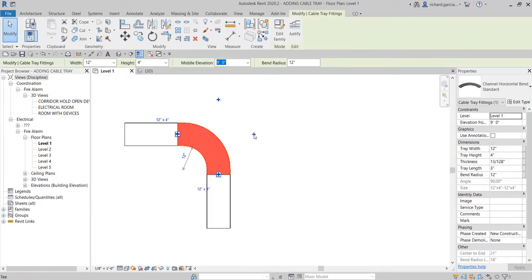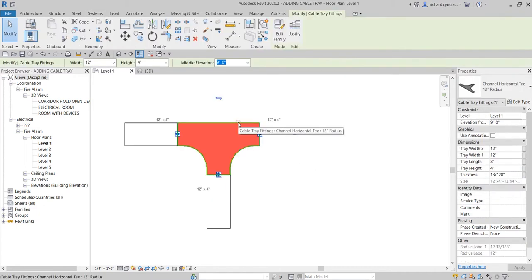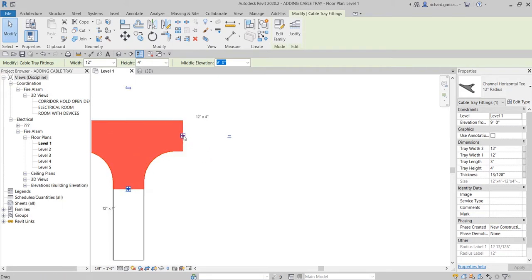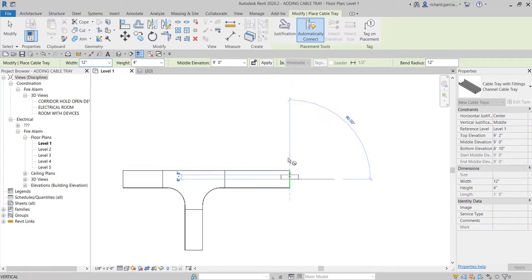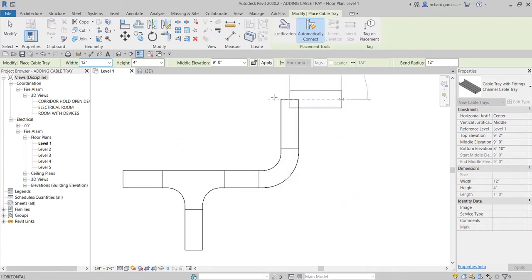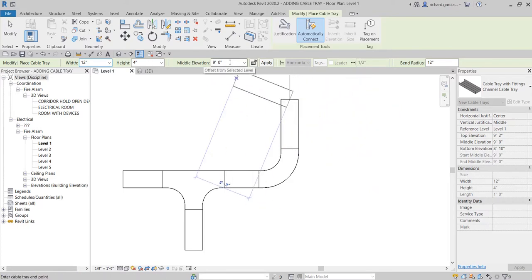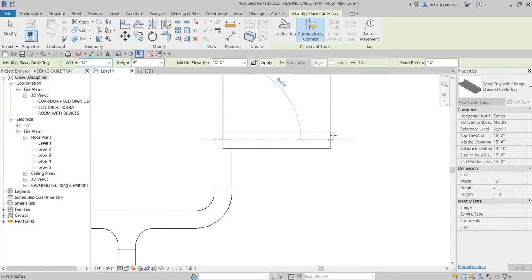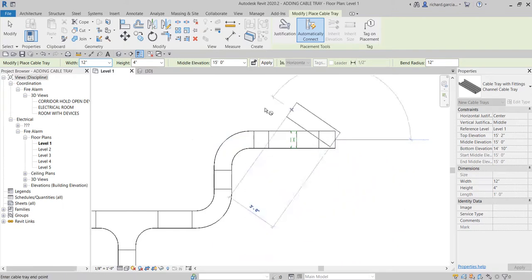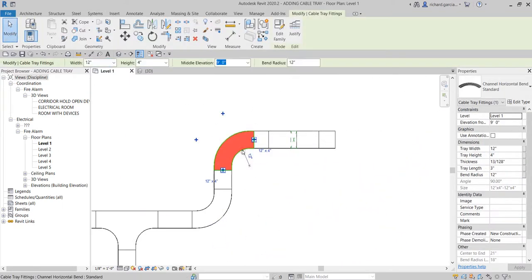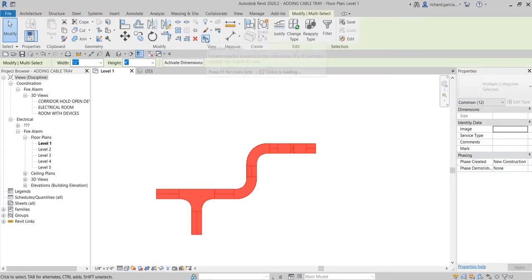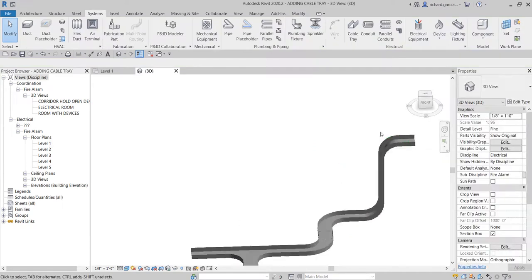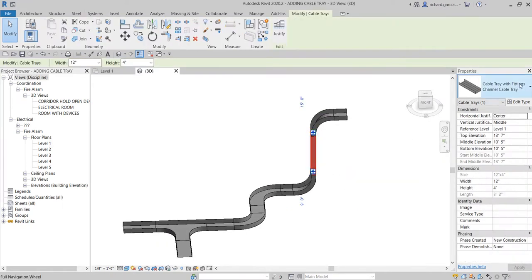This is how the channel cable tray with fittings looks. You can click an elbow and convert it to a T-fitting. You can also right-click a node and create a new cable tray from that point. To create a riser, change the elevation — for example, from 9 feet to 15 feet — then click another point. A riser symbol will appear. You can select the whole assembly and use the Selection Box to view it in 3D.